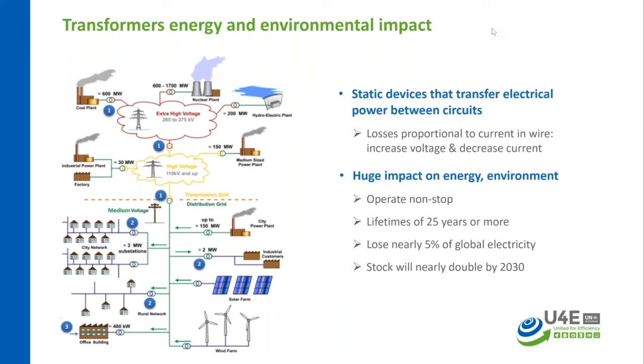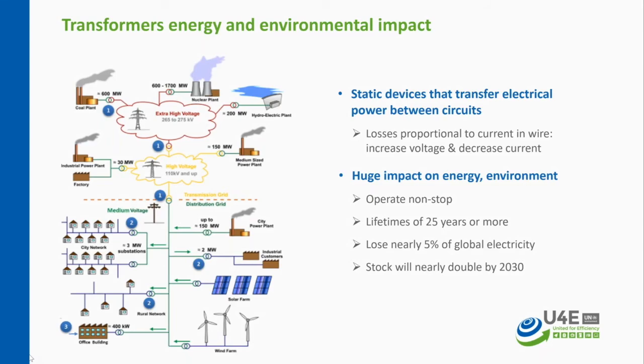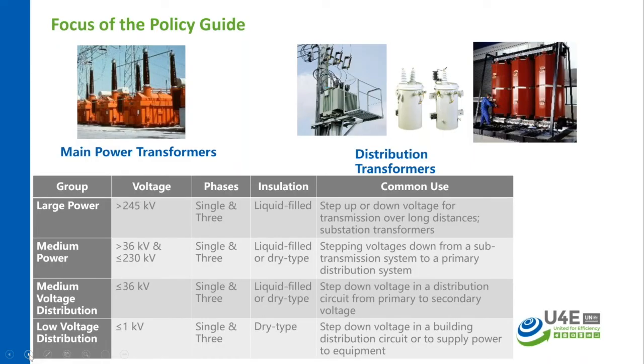Going forward, when we talk about the transformer policy guidebook, it contains the two most common types of transformer. The first is the liquid-filled transformer, which generally has two windings for stepping up or stepping down, and these are insulated with liquid, which is normally mineral oil, but nowadays with the esters coming in, this is an alternative, and sometimes natural ester is preferred as a green recyclable material. So the first category is the liquid-filled transformer, which is covered in the guidebook.